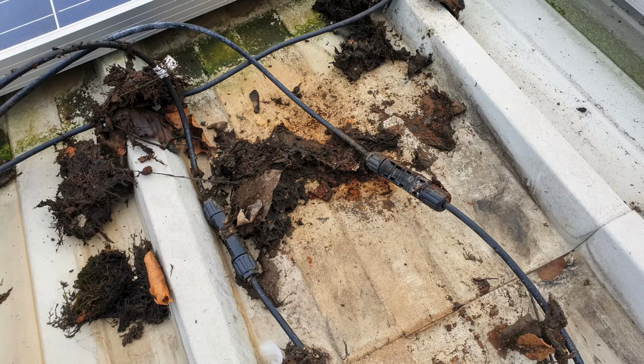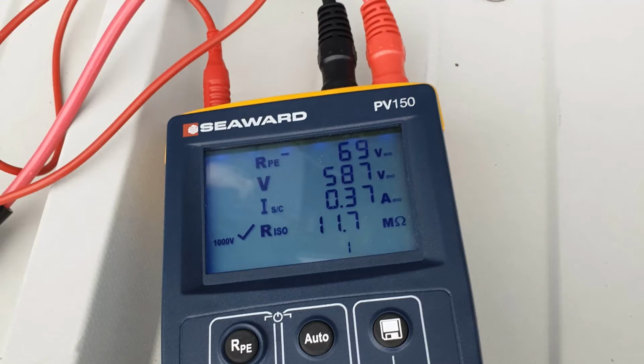I found a broken one, replaced it, tested the string, it now had a much more sensible reading, reconnected the string to the inverter, tested every string was generating, because you'd be amazed how many times you see strings that can never have been plugged in, then had 10 minutes to kill, waiting for the site manager to return to let me down from the roof.